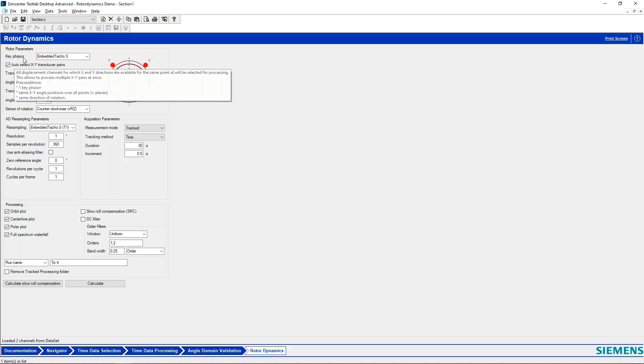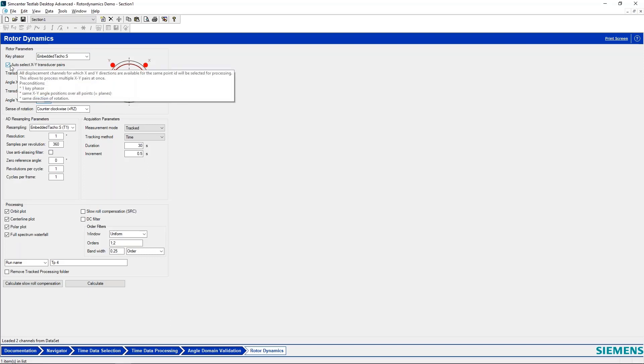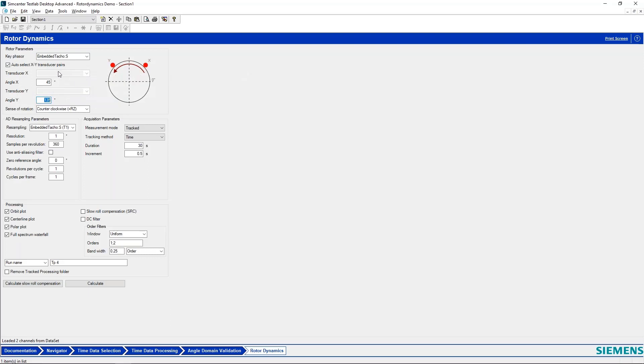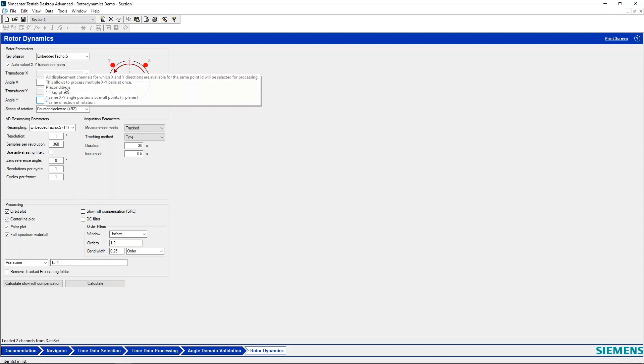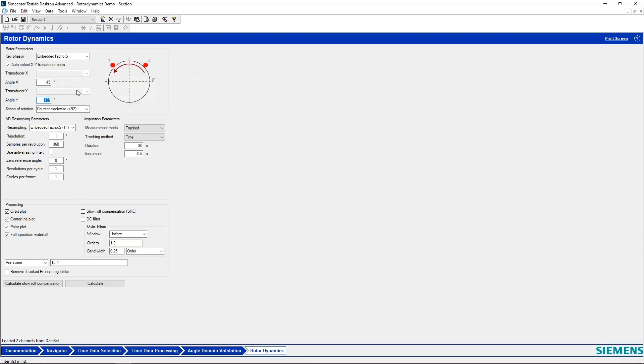So here I select my key phasor sensor, I select my key phasor orientation, my sense of rotation, and then I have auto-select XY transducer pairs on. If you name your sensor such that it has the direction of the sensor, XY and so on, we can auto-select those sensors for you. So you could analyze multiple XY transducer pairs at the same time. The way this works then is you resample the information into the angle domain.